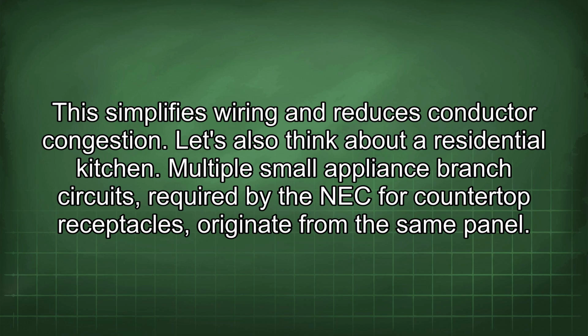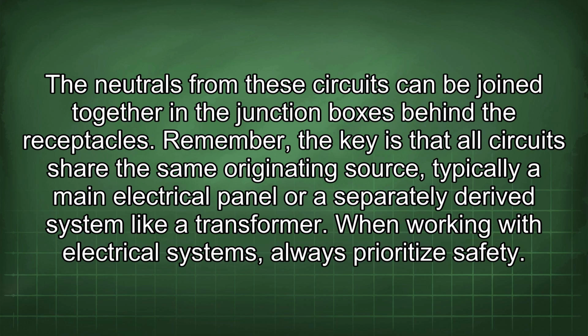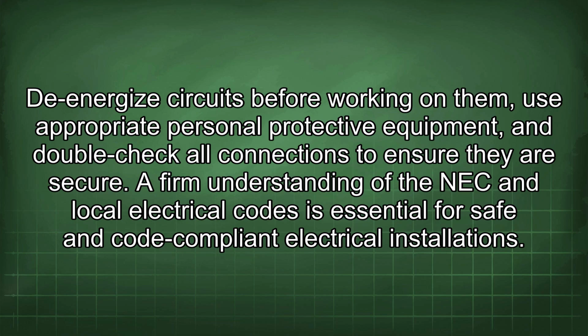Let's also think about a residential kitchen. Multiple small appliance branch circuits required by the NEC for countertop receptacles originate from the same panel. The neutrals from these circuits can be joined together in the junction boxes behind the receptacles. Remember, the key is that all circuits share the same originating source, typically a main electrical panel or a separately derived system like a transformer. When working with electrical systems, always prioritize safety. De-energize circuits before working on them, use appropriate personal protective equipment, and double-check all connections to ensure they are secure. A firm understanding of the NEC and local electrical codes is essential for safe and code-compliant electrical installations.